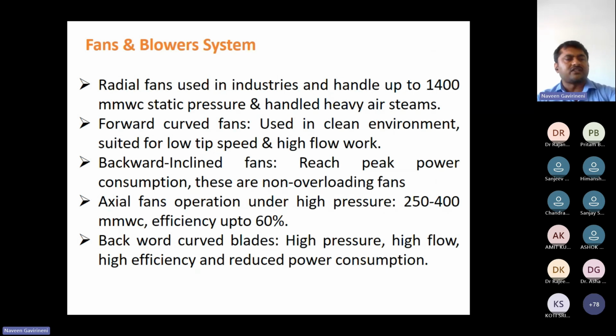The second system is fans and blowers. We have three types of fan arrangements. You just see the difference. Radial fans are used for industrial applications up to 1400 mm of static pressure; radial fan, forward curved blades.